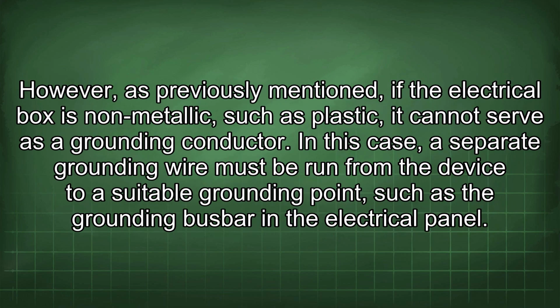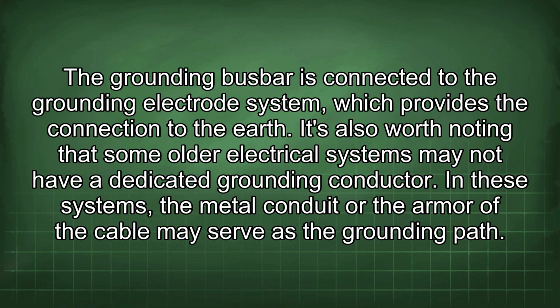However, as previously mentioned, if the electrical box is non-metallic, such as plastic, it cannot serve as a grounding conductor. In this case, a separate grounding wire must be run from the device to a suitable grounding point, such as the grounding busbar in the electrical panel. The grounding busbar is connected to the grounding electrode system, which provides the connection to the earth.